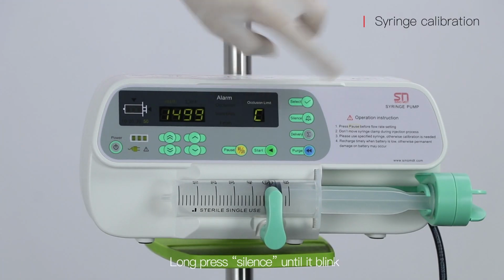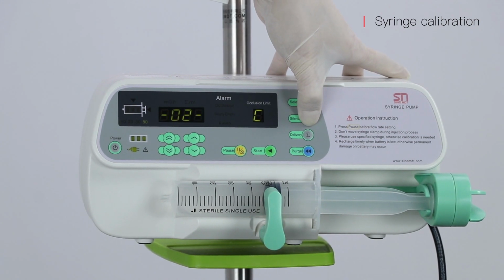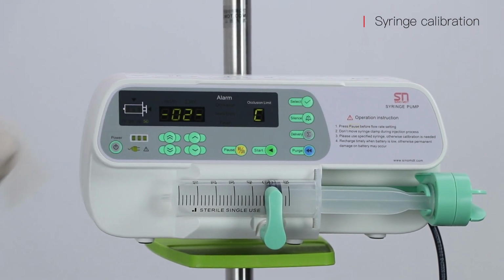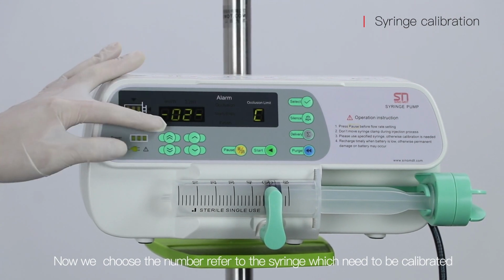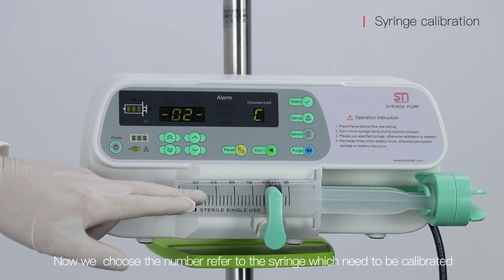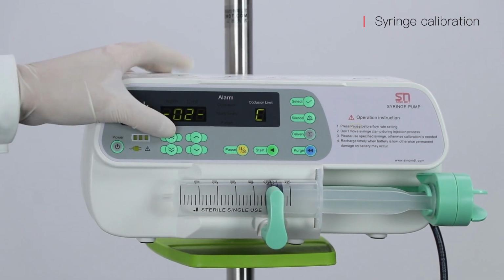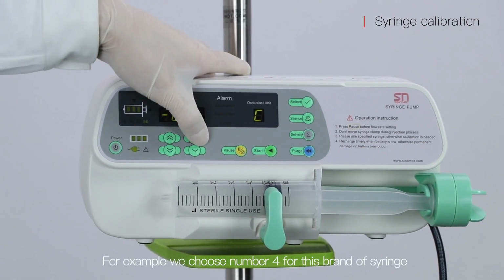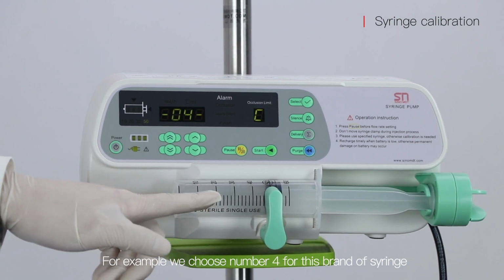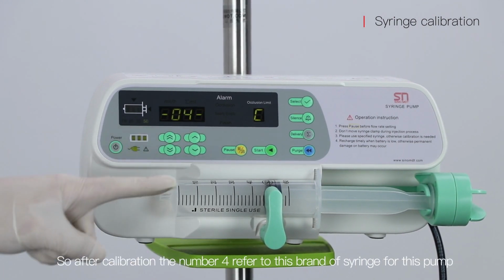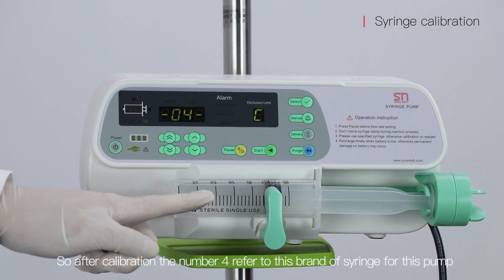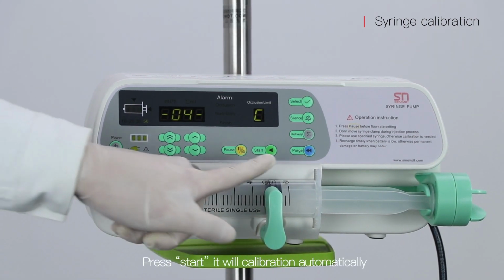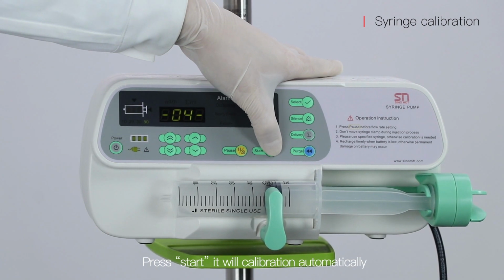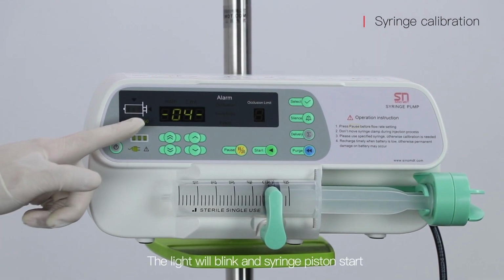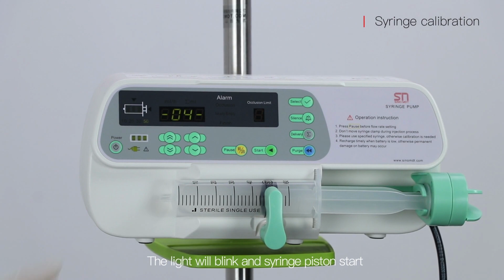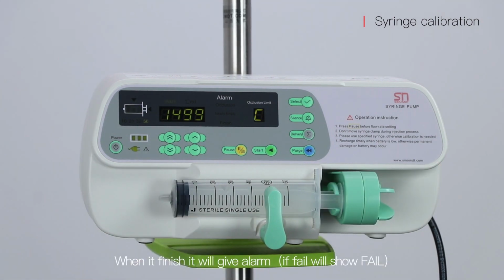Long press silence until it blinks. Now we choose the number referred to the syringe which needs to be calibrated. For example, we choose number 4 for this brand of syringe. So after calibration, the number 4 refers to this brand of syringe for this pump. Press start, it will calibrate automatically. The light will blink and the syringe piston starts. When it finishes, it will give an alarm.